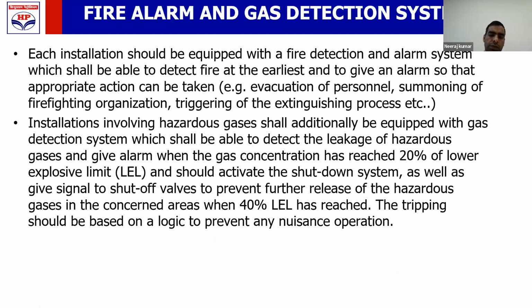If your electrical substation or your electrical installation is located near the hazardous area, then in addition to providing fire and smoke detection, you are also supposed to provide hydrocarbon detection. In case this hydrocarbon is detected, this system should be connected to your AHU damper. So on detection of hydrocarbon, your AHU damper should automatically close to cut the supply of fresh air from outside, and along with fresh air, the supply of hydrocarbon will also be cut.